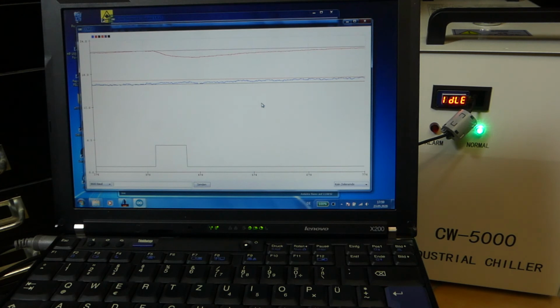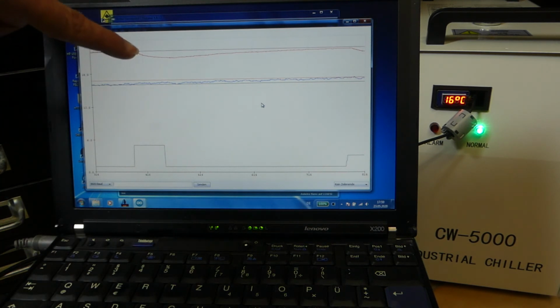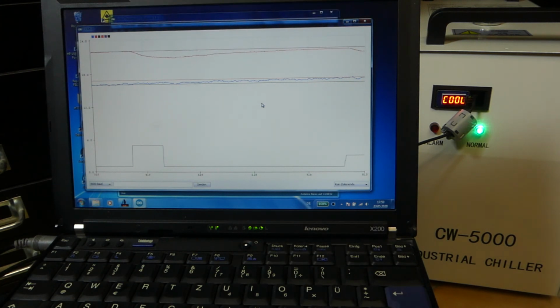So the water temperature is staying rather well within its temperature window, and now it just tripped, so it's going to start the cooling cycle. But if I remove the energy that builds up inside of the case of the chiller, I can actually make the water stay cool for a lot longer than it did before. And that was a very simple code change, and it really made a lot of sense. And as you can see, we're getting really rapid drops every time that the fan turns on. So there is some heat storing inside of the case.